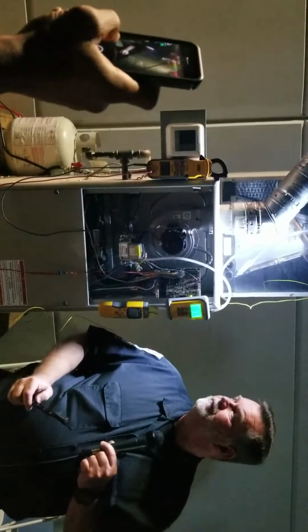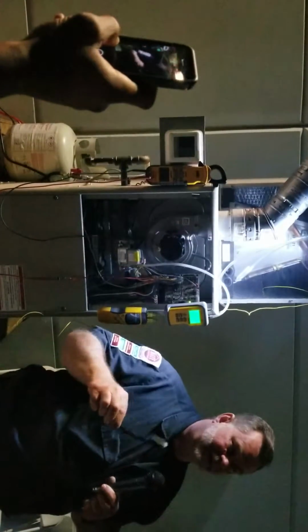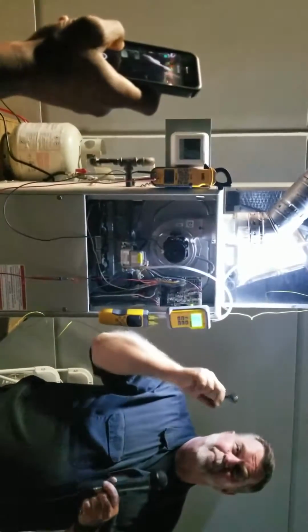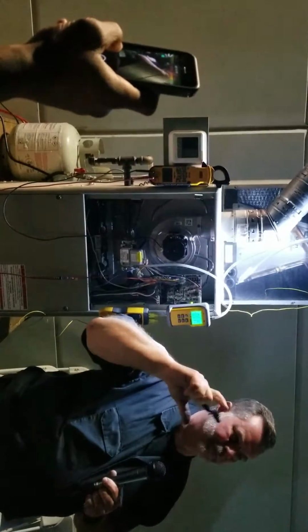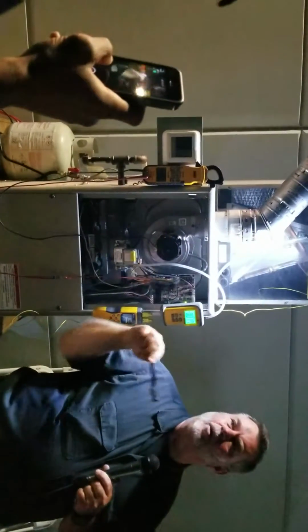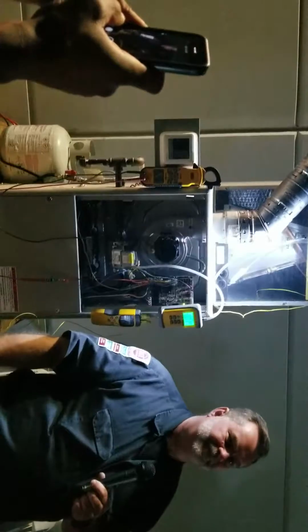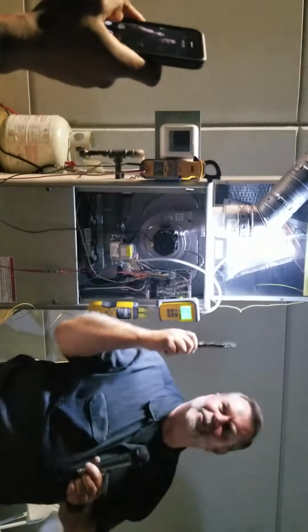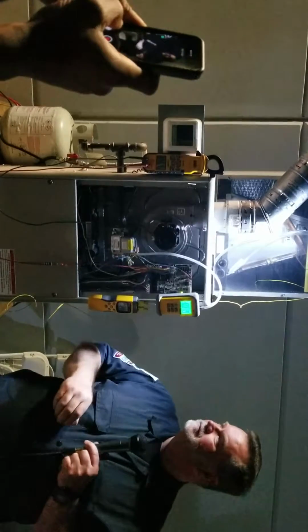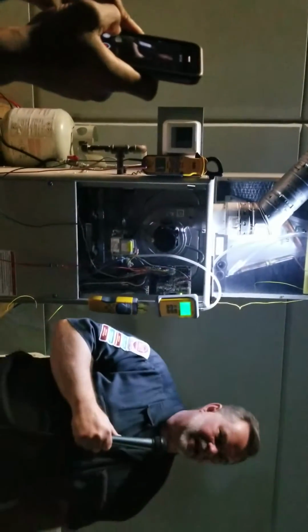Here's what happens. The silica gets deposited on the rod. The silica, right, Oscar? That silica then, in microscopic particles, gets burned into the metal rod from the flame, and it becomes more insulated because the silica creates a microscopic coating. And while it'll work, it won't work as long and you'll have to clean it again, and then you'll have to clean it again, and again. Sounds like a barbecue grill, man. I know. Use the stainless steel brush, guys. It doesn't leave anything. Right, Oscar? Oscar's one of my colleagues, by the way. Yes, it turns into glass. The silica turns into glass, and glass is an insulator. All right? That makes sense?